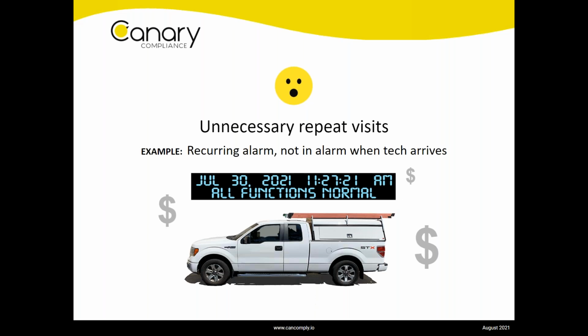Another example is repeat visits. A lot of times an alarm goes off, a service call gets made, a technician shows up on site, and they find nothing wrong with the Veeder-Root, everything's functioning normal, and then they leave. The problem is that alarm may have been due to bad wiring in a probe or sensor, or it's going in and out of alarm with some frequency.